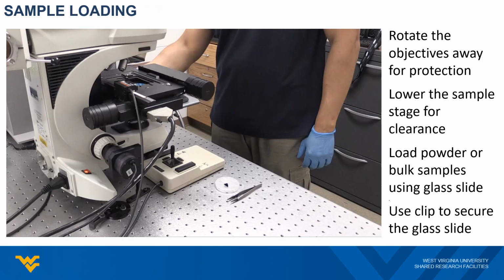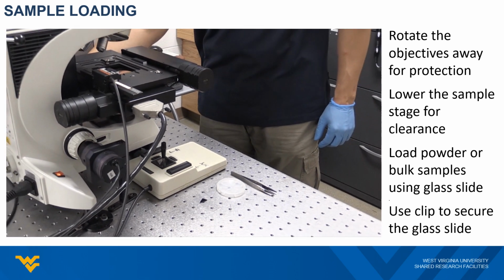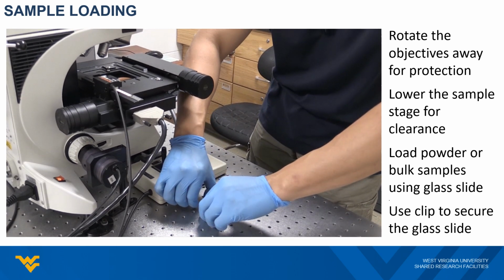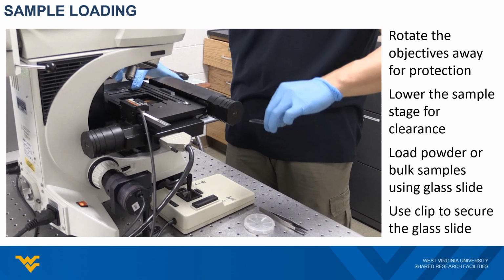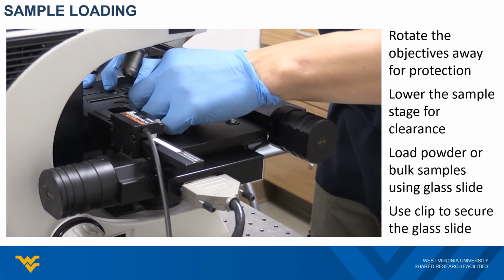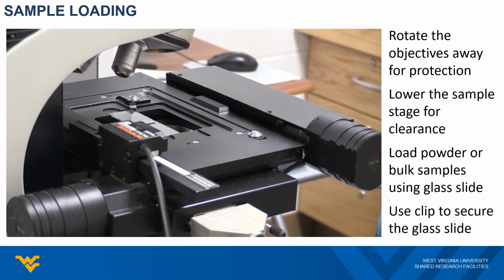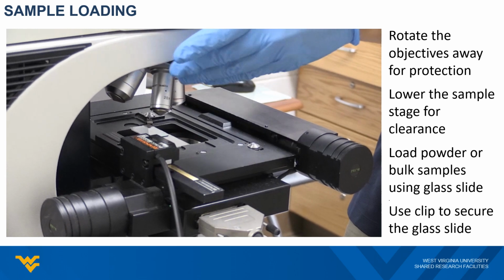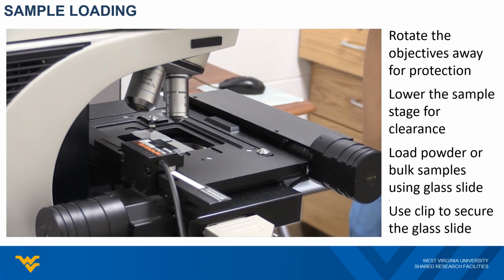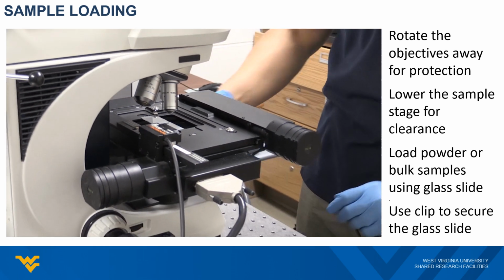You need to put your sample on top of a glass slide for measurement. For bulk sample, you just need to drop your sample on the glass slide and make the surface to be measured facing up. For powder sample, please use a spatula to press your powder sample to form a nice and flat surface. To load your sample, first rotate the objective away and also lower the sample stage all the way down to get enough space for sample loading. Then you will need to mount the glass slides on the sample stage and secure the glass slide using a side mantle clip. After sample loading, rotate the objective back to observation position and start the visual alignment.